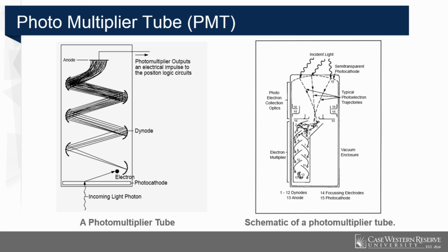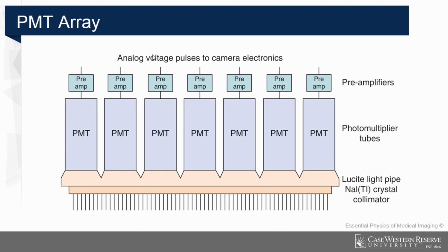It's a cathode. And once the photon hits the photocathode, it will emit an electron, and it will go through an array of dynodes, what we call dynode array, to get signal amplification, which is needed so the output current will be strong for input for further imaging process.